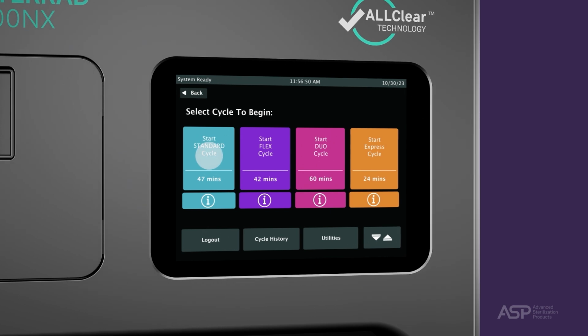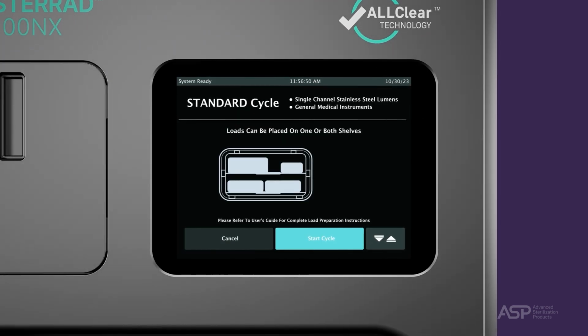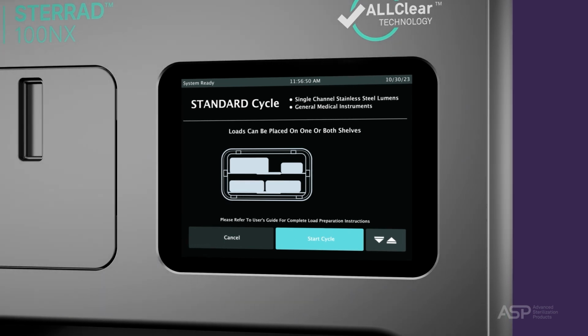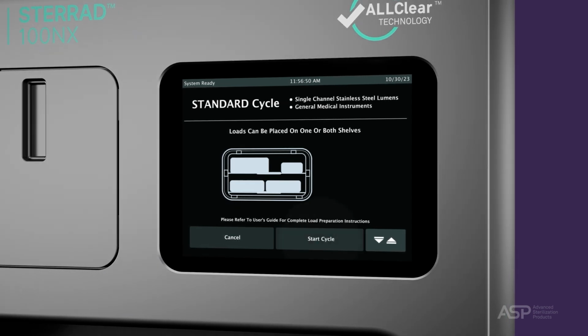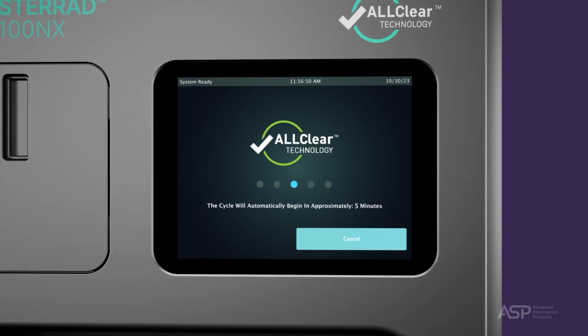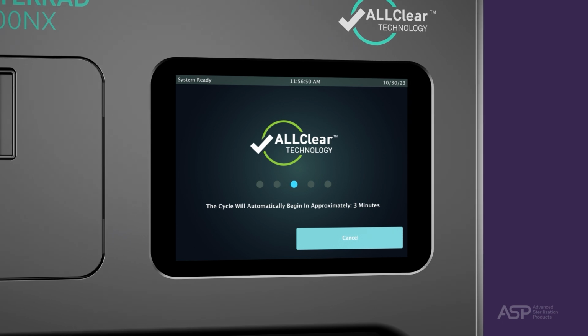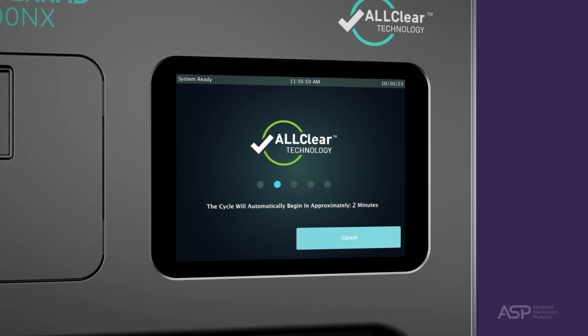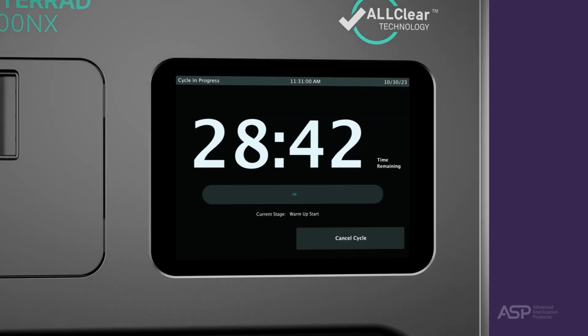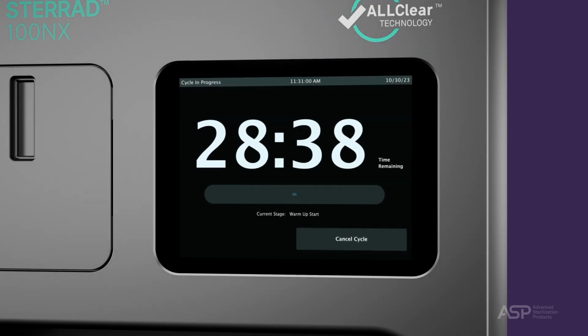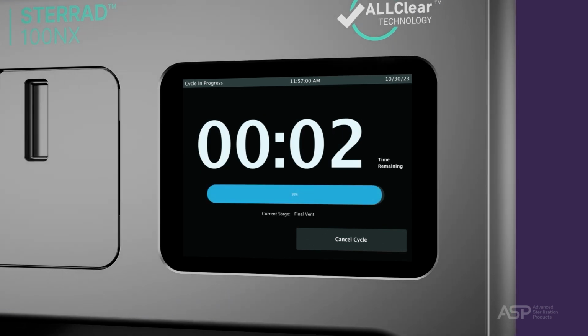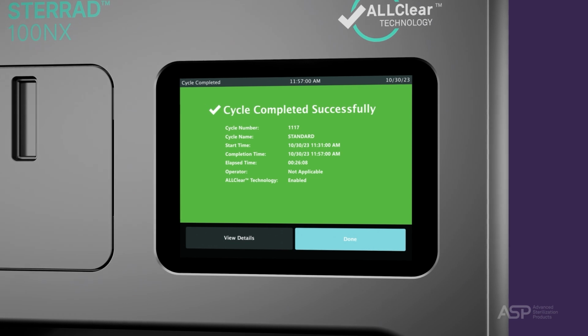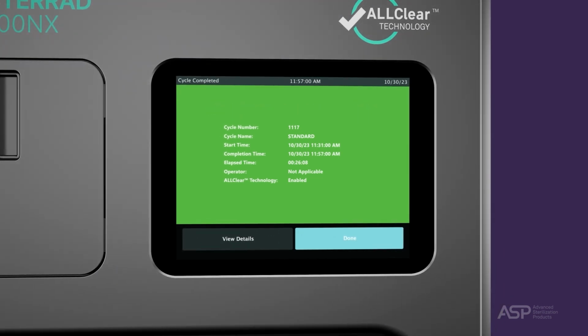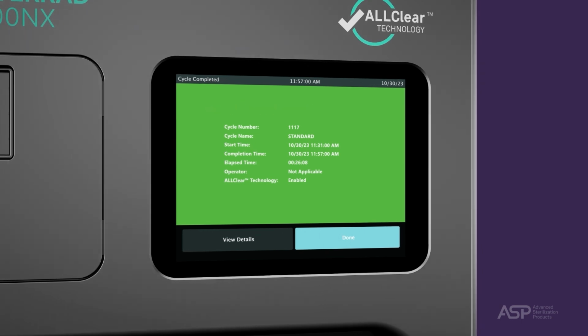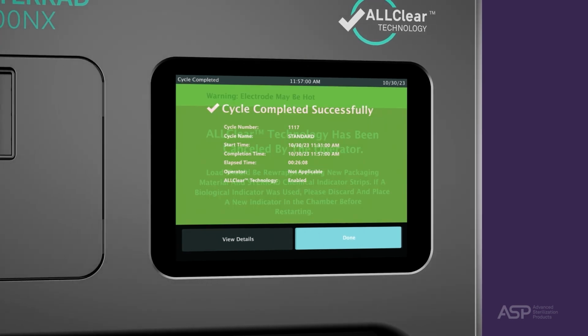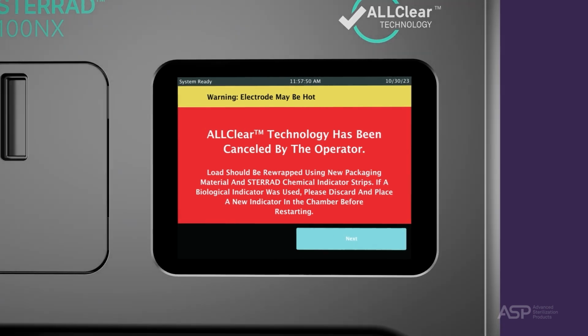As a reminder, after selecting a cycle, the system will instruct the operator to load the chamber. The screen will show instructions on how to load the chamber per the selected cycle. Select the desired cycle and press Start. The ALLClear technology process begins and is displayed on the monitor. This is a load conditioning process that minimizes the number of sterilization cycle cancellations by detecting system problems and correcting load issues. Once the ALLClear technology process completes successfully, the sterilizer starts a countdown clock and begins the sterilization. When the cycle is complete, the green Cycle Completed screen is displayed, indicating a successfully completed cycle. In addition, the STERRAD 100NX Sterilizer with ALLClear technology loudspeaker emits one long beep. A series of 10 short beeps indicates a canceled cycle.